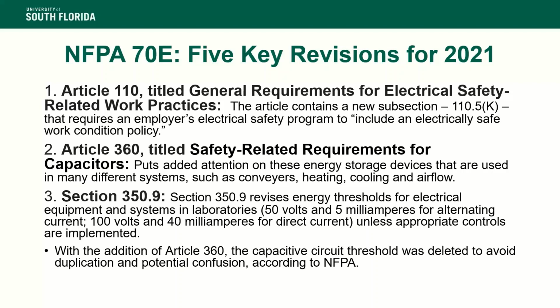Article 360 is titled Safety-Related Requirements for Capacitors. Again, this is where they've added more attention to these energy storage devices such as conveyors, heating, cooling, and airflow. Section 350.9 has been revised to include energy thresholds for electrical equipment and systems in laboratories. At the bottom of the bullet statement, the capacitive circuit threshold in Article 360 was deleted to avoid duplication and potential confusion, according to NFPA.